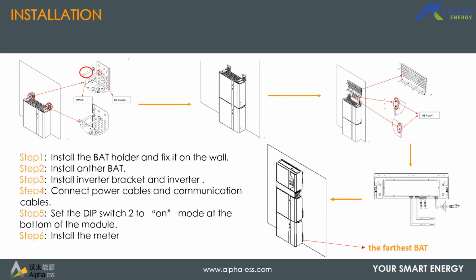To put on the inverter, you just hook it on the bracket, and then it would hold firmly, supporting on the battery module as well. So once you install your battery holder and fix it on the wall, and then you install another battery if you have 2 batteries, and then install the inverter bracket, as I said, and then you connect your cables, your battery cables, your internet cables, your battery comms cable, and then from there you would need to do a few settings on the battery, on the bottom battery or the last battery on the chain.